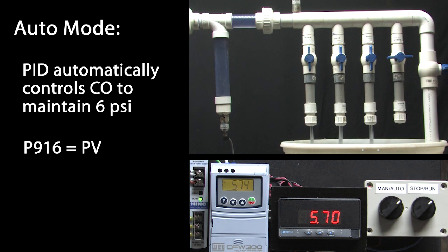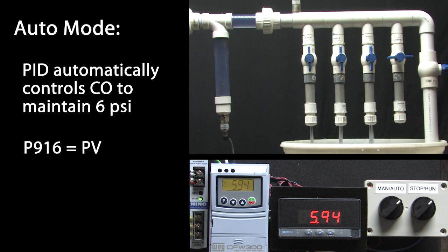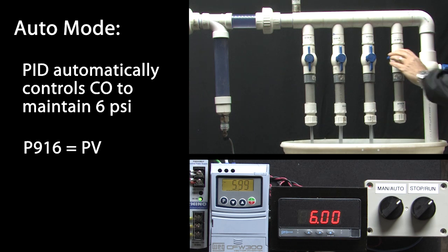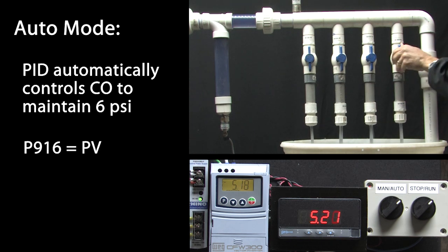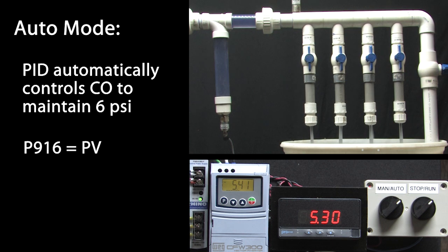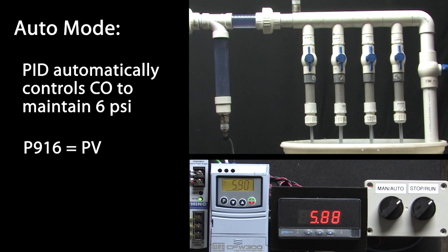How about three valves? Again, give it a few seconds. And sure enough, it settles out right at 6 psi. Four valves? Sure enough, it ramps up and settles out right at 6 psi.